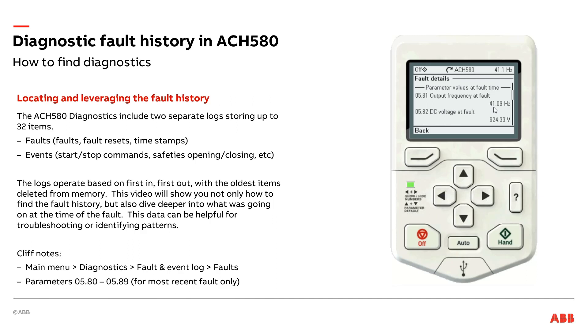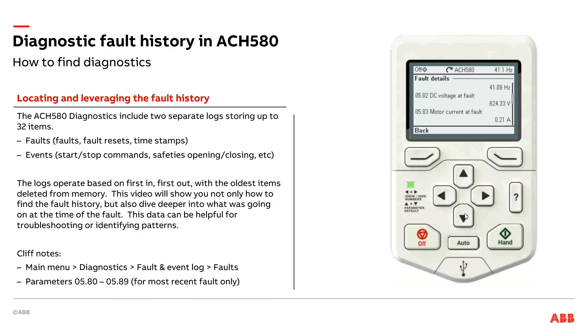Scrolling down, I can see what information is available to see how the drive was responding at the time of fault. I can see that I was running at 41.09 Hertz when it faulted. I can also see the DC bus voltage, which is always a handy item for troubleshooting — it can help give you some indication if maybe there's a problem on the incoming power quality, or maybe you were trying to slow down a very large load too quickly with a lot of inertia regenerating back to the drive, pumping up the DC bus voltage.